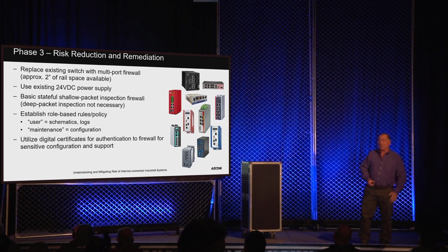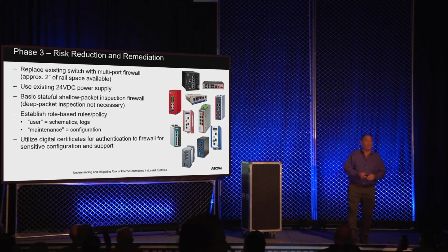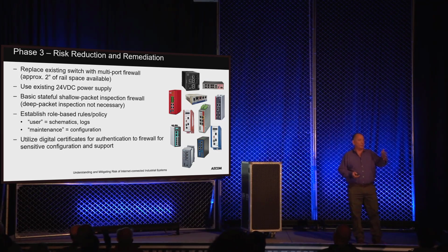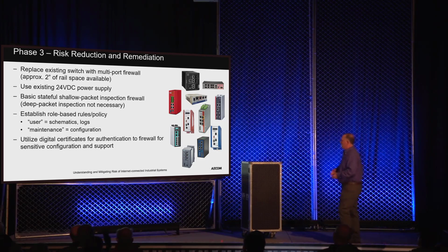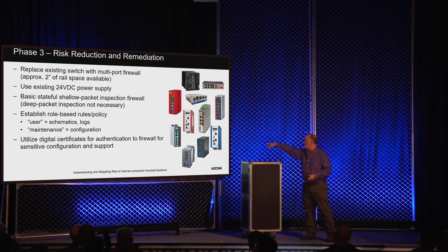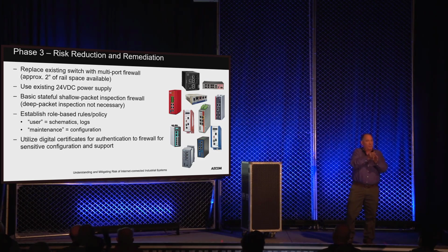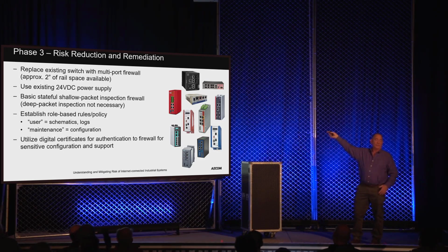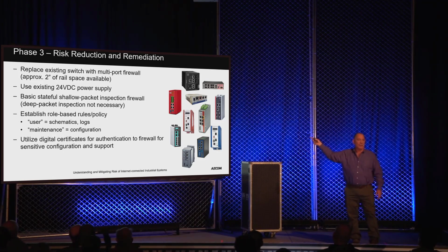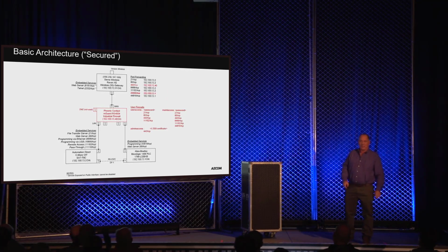So I'm like, this is cool. So I ended up going with the mGuard product from Phoenix Contact, because they have a firewall, just like Hirschmann, everybody else, that has integrated switches. So you kind of see those varieties. There's the Moxa one down there on the lower left. So it gave me the capability. The reason I wasn't able to pick any of these other ones, some of these products, like one of the most powerful ones there, this is the Cisco ISA on the top, but it's also significantly wider than the room that I had. So what was really cool, very easy project swap.